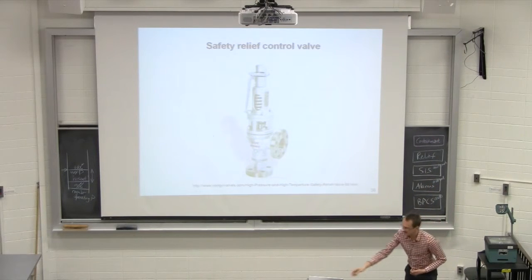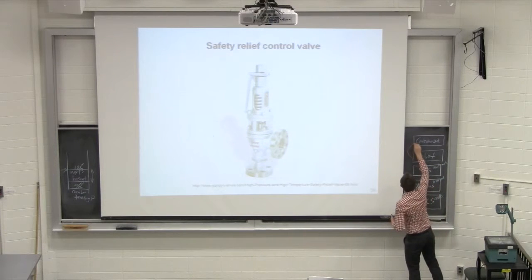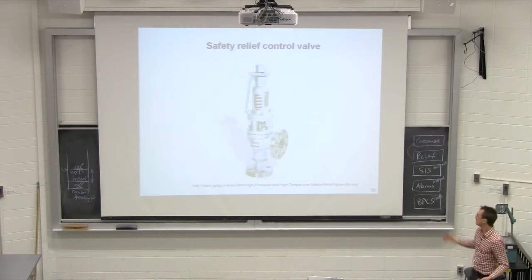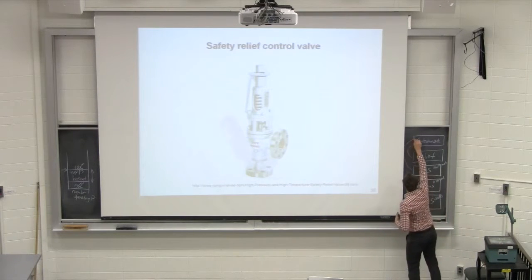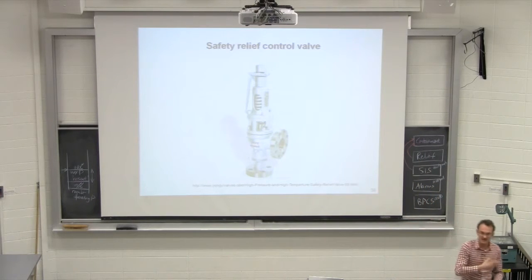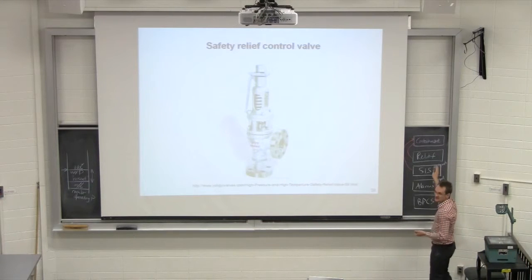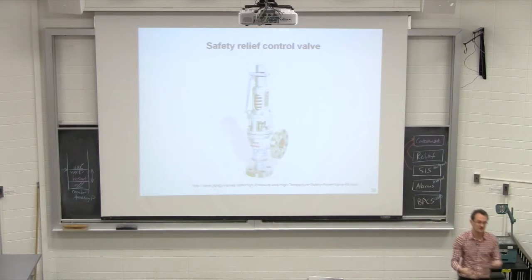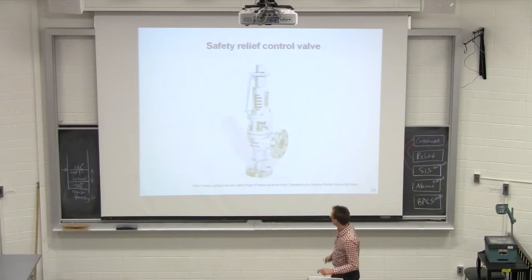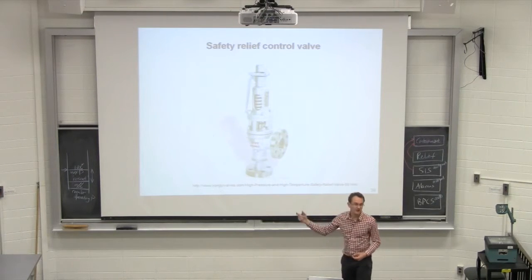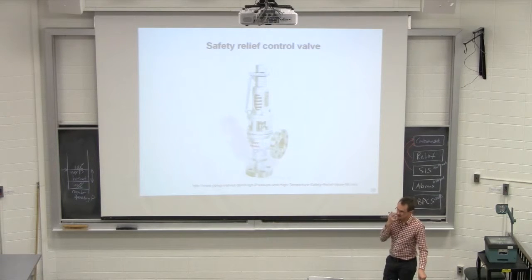When we talk about relief, we also have to consider containment. Something that can contain what's being relieved. That final layer is designed to have certain material relieving to one container and other material relieving to a different container. So if you're dealing with a large refinery, you'll have several vessels to accept various relief gases or liquids. This discharge pipe can often have several kilometers of piping to get to the final containment site.